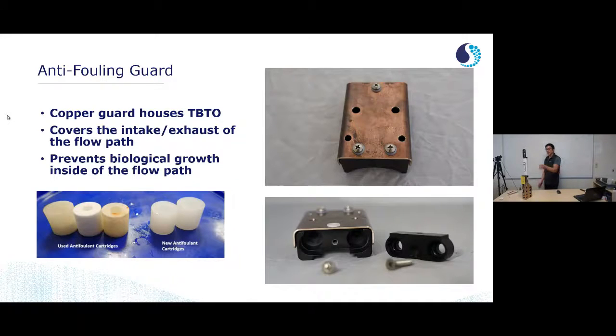So I would like to talk about the Antifouling Guard on the instruments. That is this guard you can see on the right. Currently on my instrument, I have this sticker on it. This is a brand new HydroCAT EP. And so we ship it with this sticker covering up the holes for the intake and the exhaust for the flow path to prevent these anti-fouling cartridges from leaching any toxic chemicals out. And so always remember to take this sticker off before you deploy it, otherwise you won't get water into your system. So that's what I'm going to do first thing, just pull off the sticker.